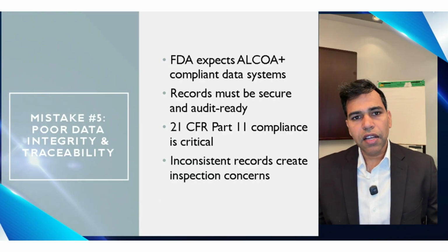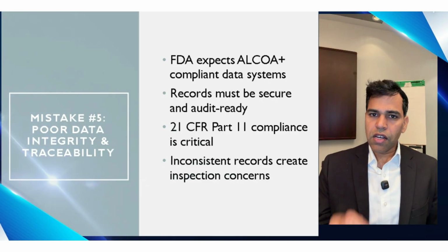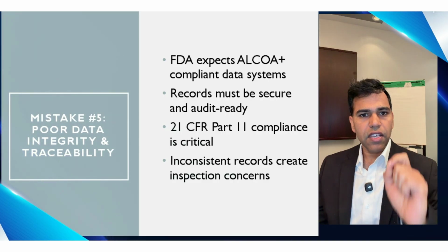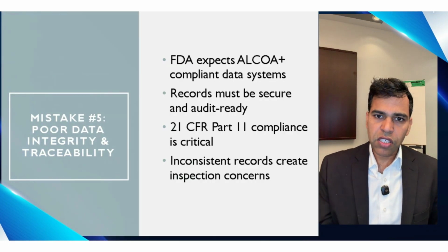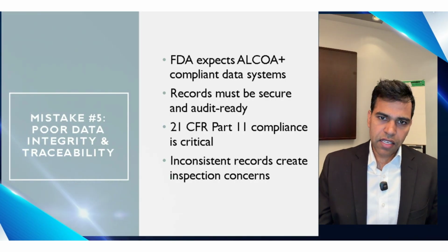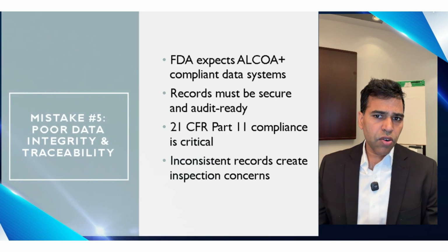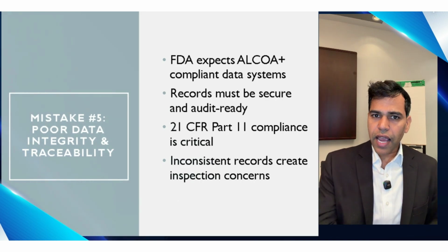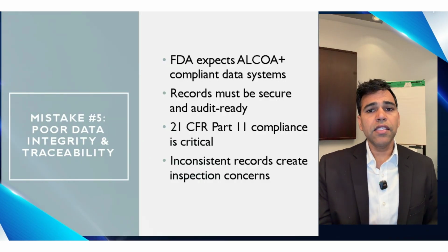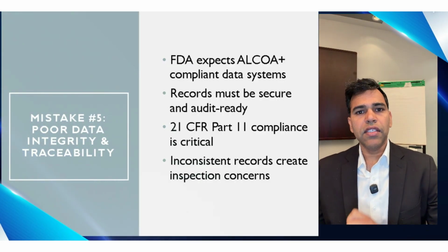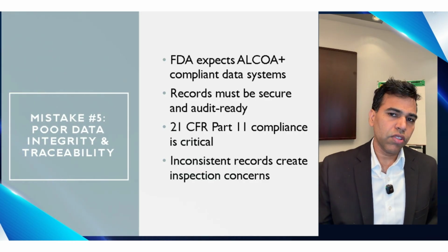21 CFR Part 11 compliance for electronic records, audit trails that are complete and unaltered, data that's traceable from raw instrument output all the way to your submission. These aren't optional extras. They are baseline expectations. Inconsistent records, overwritten data, or gaps in audit trails are serious inspection findings, and increasingly, FDA is scrutinizing data integrity not just during inspections but in the review process itself.